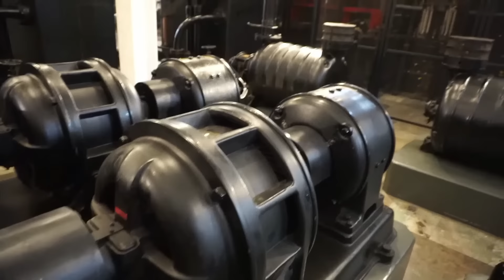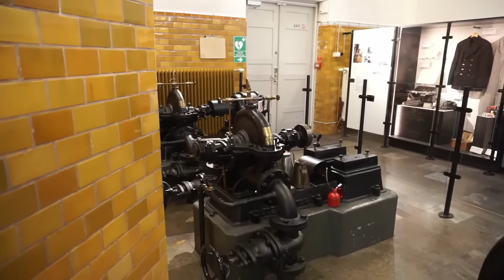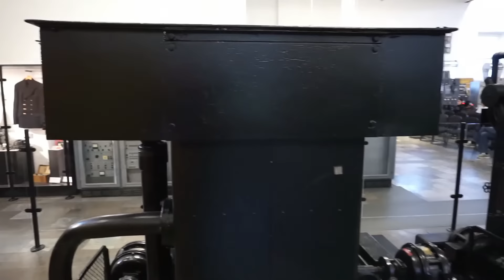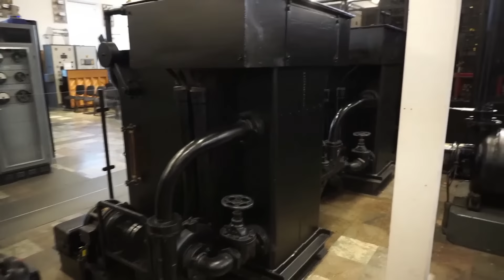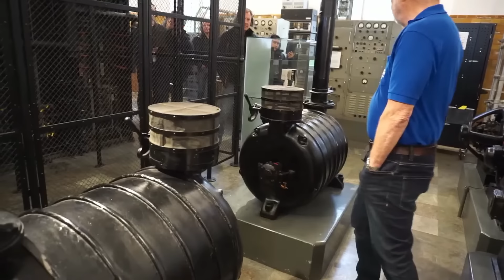Down there we have centrifugal pumps for cooling. I'll tell you more about them later on. And here we have rheostats for controlling the rotor resistance in the main motor. Controlling the motor speed creates a lot of heat on our contactors. And here we have 2 cooling fans that provide compressed air to blow out electrical arcs and to cool the contactors.